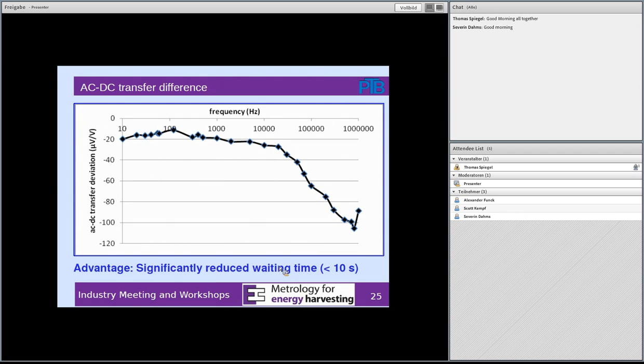I mentioned you have to repeat AC-DC transfer measurements many times to get rid of drift. Here, due to the regulating loop or control loop, everything is significantly quicker. Normally for a thermal converter you have to wait about 50 seconds to a minute; here you only wait 5 to 6 seconds—an improvement in speed of about a factor of 10. This could lead, if done consequently, to greatly reduced measurement times. Maybe we'll do that—we'll have to think it over.